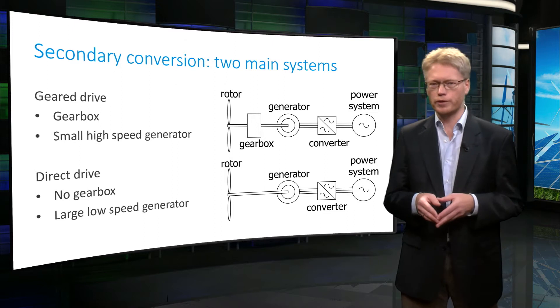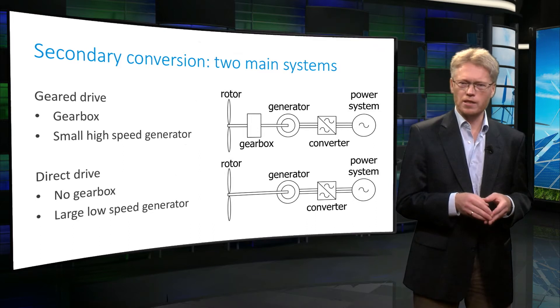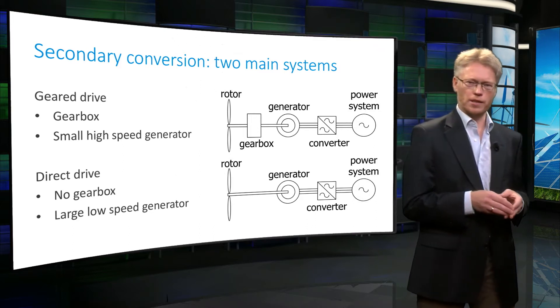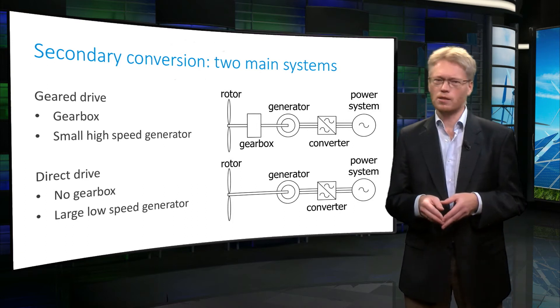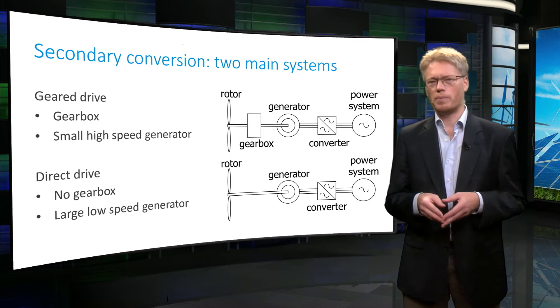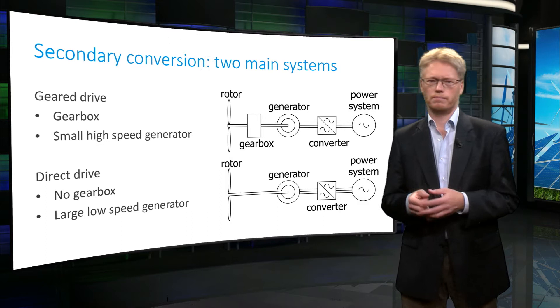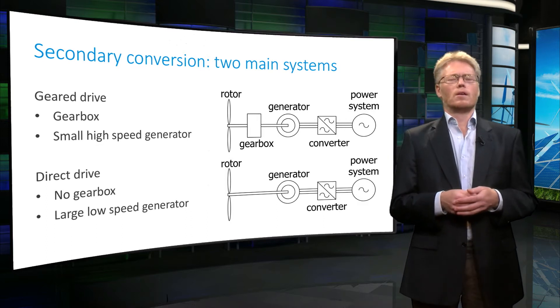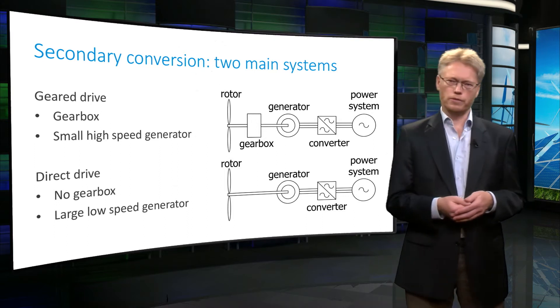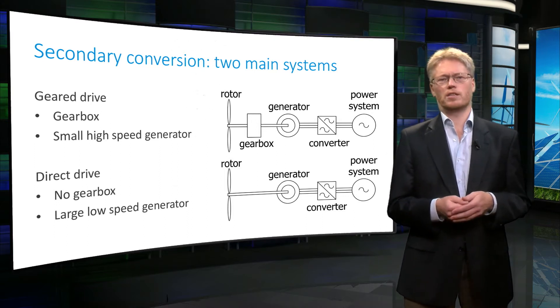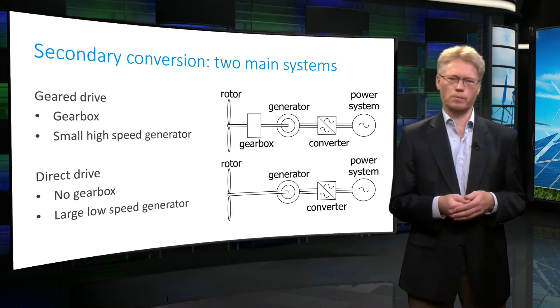Both systems need a power electronic converter for the connection to the power system. The generators operate at a varying speed and therefore generate a varying voltage and a varying frequency. The power system has a constant voltage and a constant frequency. A power electronic converter converts the varying voltage and frequency into a constant voltage and frequency. At full load, the typical efficiencies of gearboxes, generators and power electronic converters are in an order of 97 percent. At partial load, these efficiencies may decrease, especially for gearboxes.